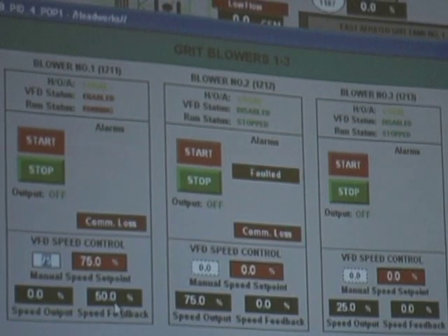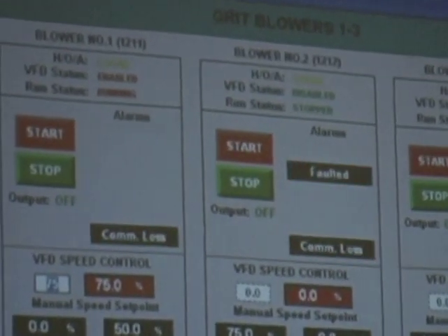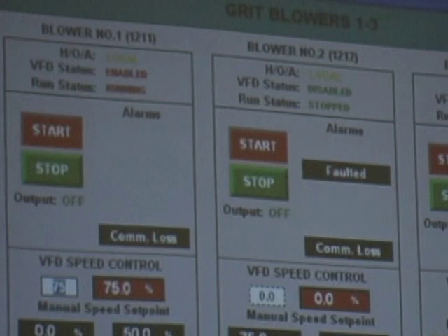Now, again, is that based on the 300 CFMs for the blowers? Yes, each blower is capable of 300. That's our set point, is where we should be running, 300 CFM. That would be 100% speed. Yes. Okay, you're looking at percentage of. That's if you're running two channels, because 300 CFM is per channel. So the blower max is 600 CFM, right? Yes. So then with one channel on at 50%, we have 300 on. And then you can verify that with your airflow.